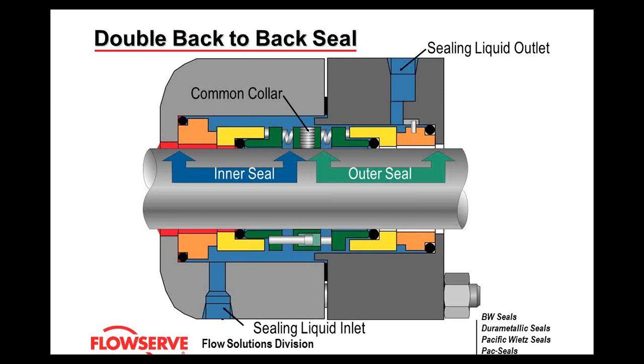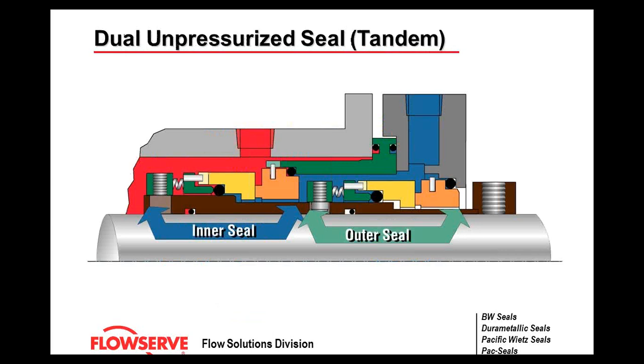The barrier fluid provides lubrication to the seal faces, especially if the pump fluid is overly dirty or lacks good lubricating properties. The old nomenclature called unpressurized seals 'tandem' and pressurized seals 'double,' but today the terminology is simply dual unpressurized or dual pressurized. It's much easier to look at your system and ask: is my barrier system under pressure? If yes, you have a pressurized system; if not, unpressurized.